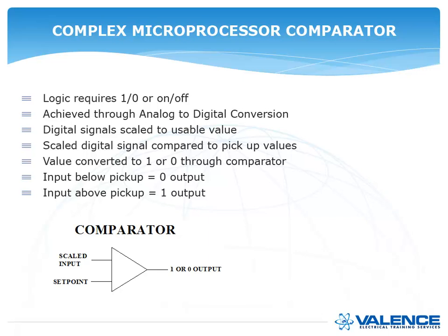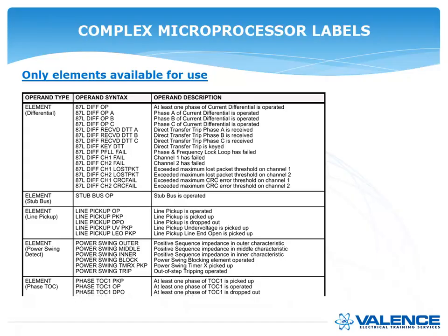So it's either on or off. That comparator will use a setting — in this case it's a GE 87 relay. If you wanted to look at the line pickup operation, that line pickup would be the set point in the comparator. You can see that GE relays use codes like 87L, stub bus op, line pickup, power swing, or phase TOC one pickup — those are all the things that you can choose in a GE relay.